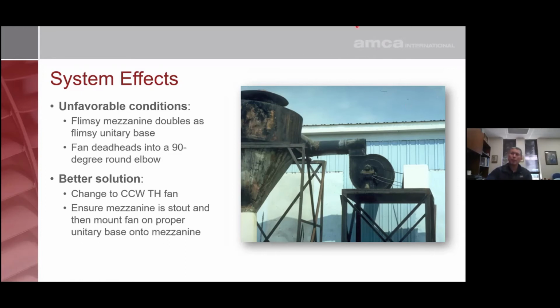Here we have an upblast fan. They use 50-gallon drum containers as a piece of ductwork functioning as a position C elbow, forcing the air into the collector. General rule of thumb, I figure that every horsepower a fan is consuming during a year, for a fan that's running continuously, costs about $600. So if you're losing, let's say, 10 horsepower because you have this improperly designed system, that's probably costing you about $6,000 a year in excess energy costs. So it's very easy to estimate what the payback of a horsepower savings is going to be over an improper design or a cheap initial purchase.